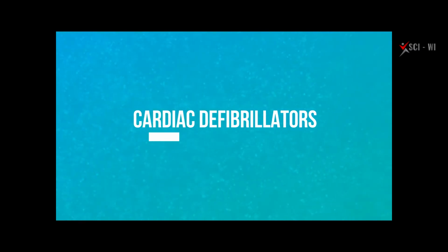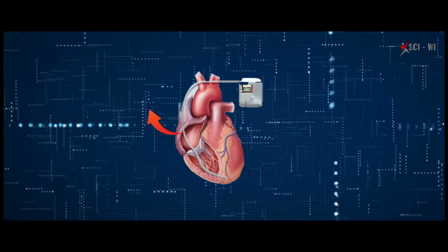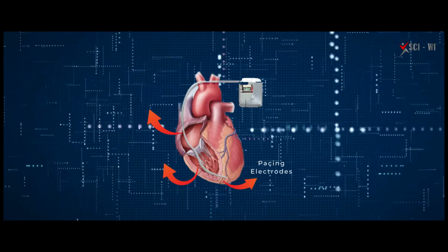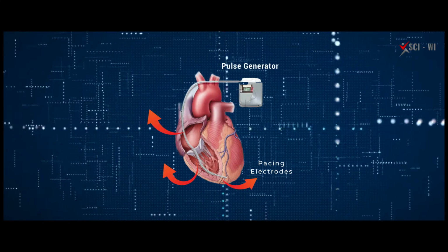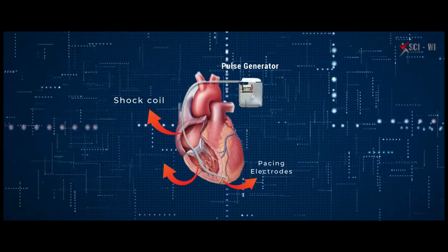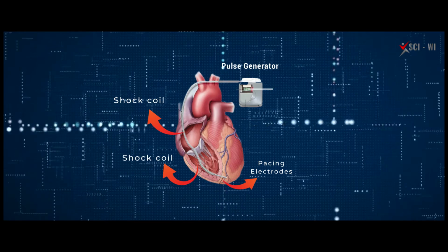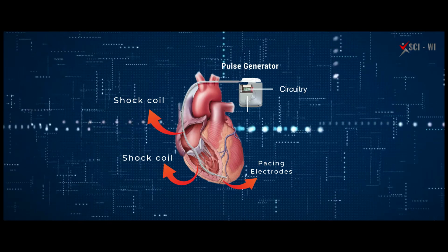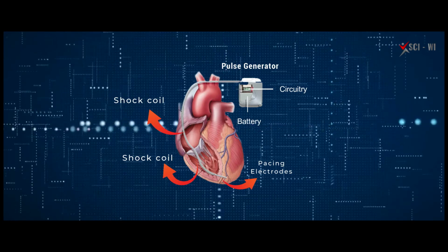Cardiac defibrillators. This is a device which is designed to store electrical energy for subsequent delivery in the form of an electrical shock. Typically, defibrillators are battery powered, but some can operate connected to an AC or DC power line.